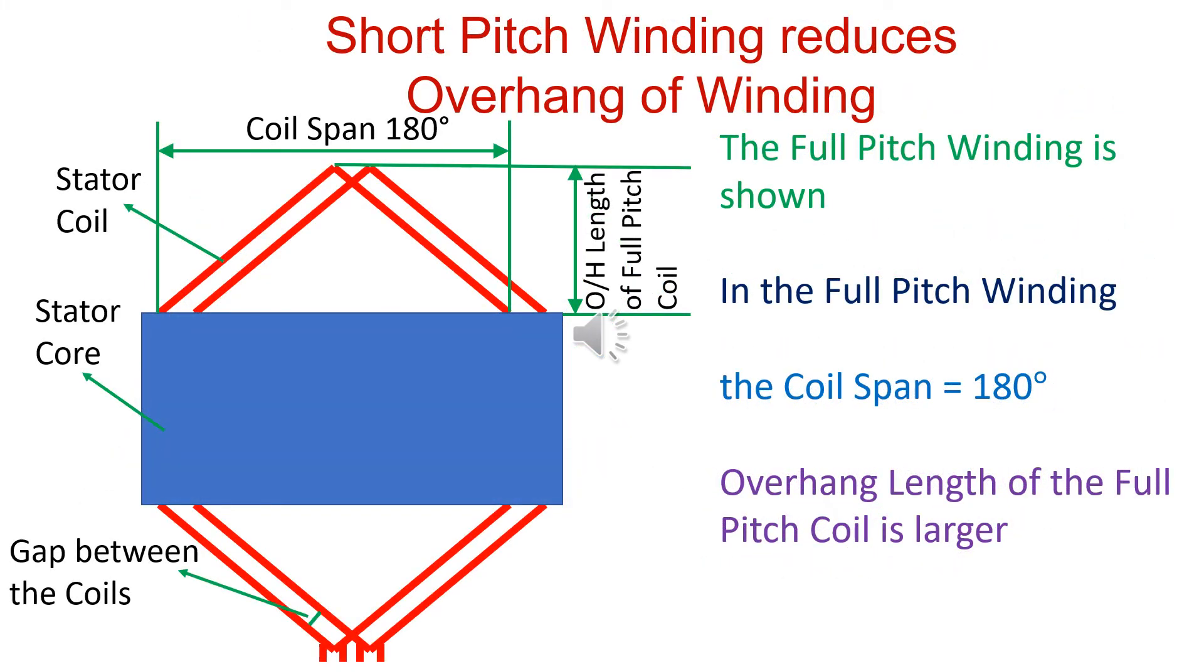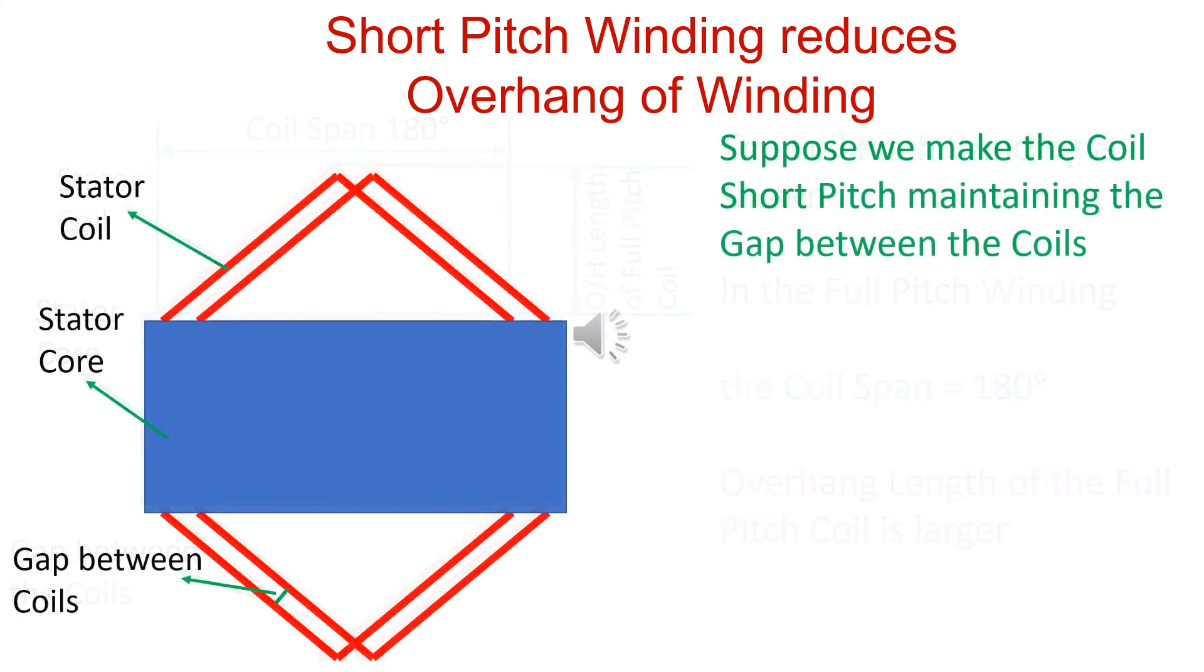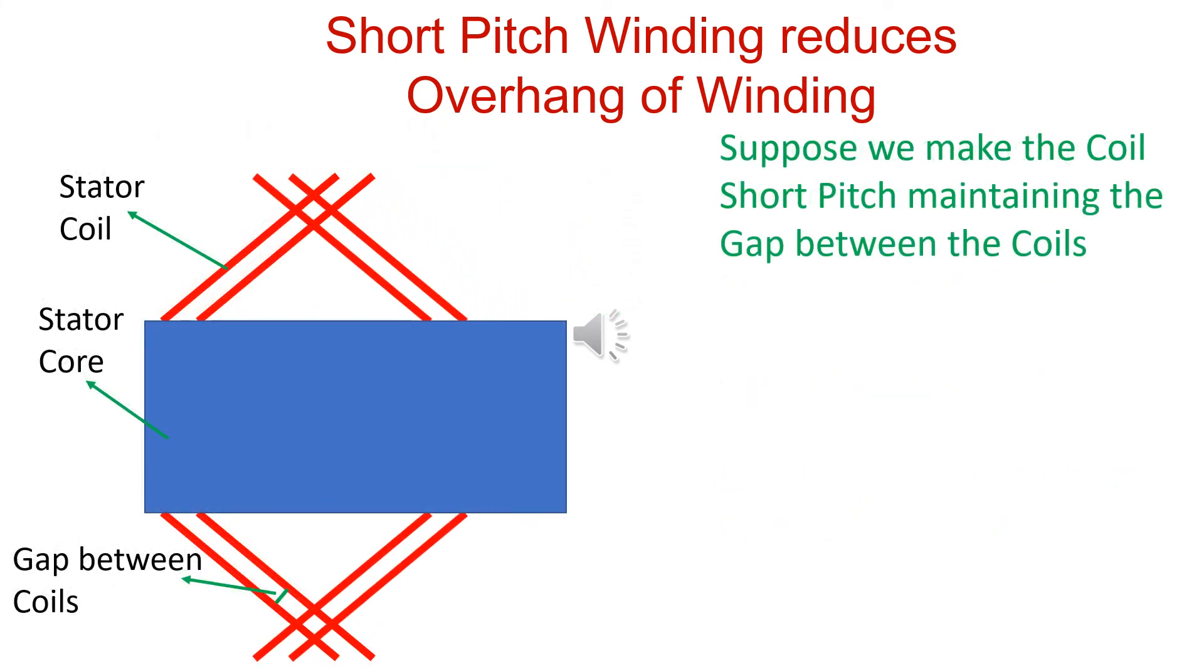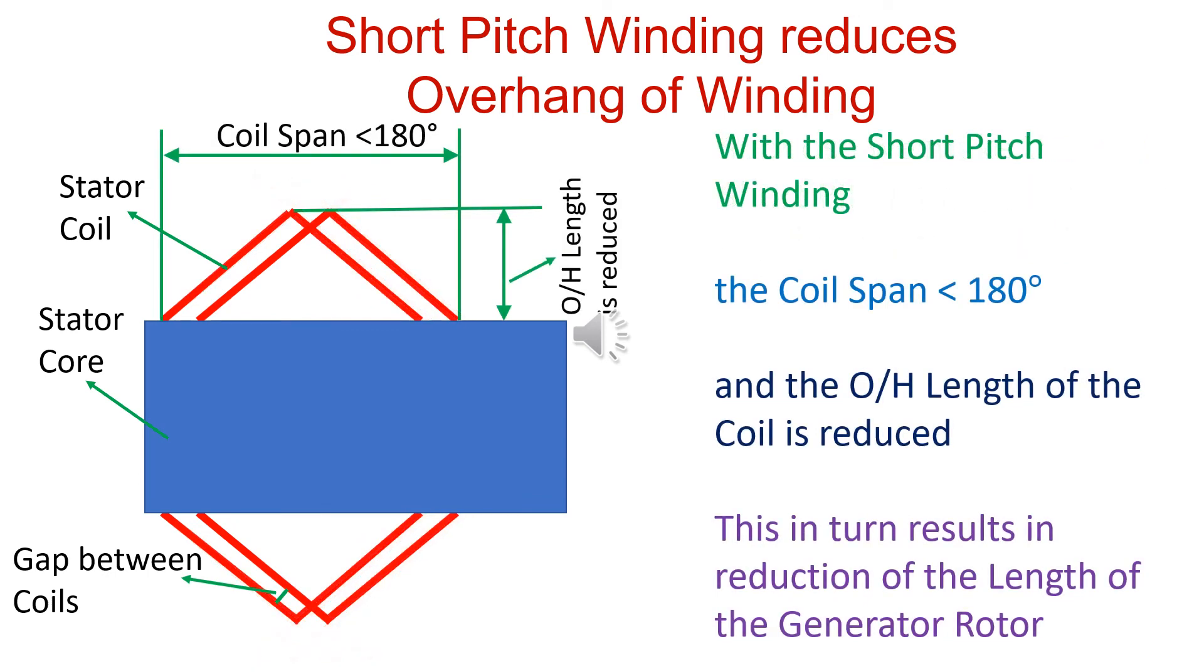The full pitch coil is shown. Overhang is larger. Coil pitch is less in short pitch, maintaining gap between the coils. Overhang length of the coil is reduced, resulting in reduced generator length.